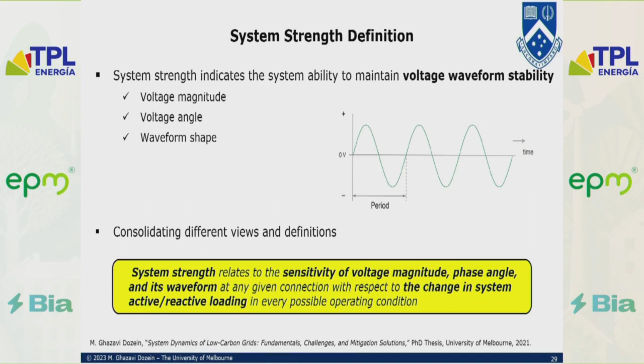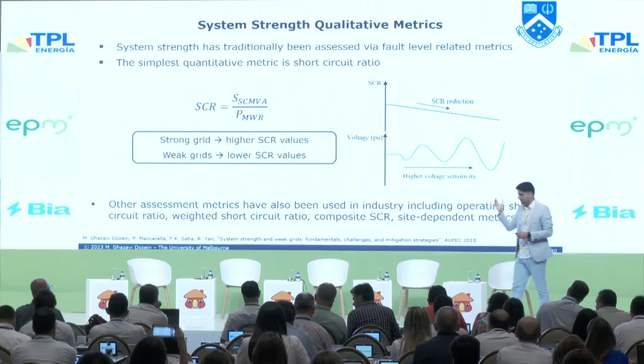System operators try to link system strength with fault level - that's another lecture in itself, how you link this to fault level. But let's accept that the system strength is related to fault level, and when the short circuit ratio is reducing, your voltage becomes wobbly, meaning more variability in your voltage, which is not desirable in system operation. There are different metrics proposed by system operators around the world.